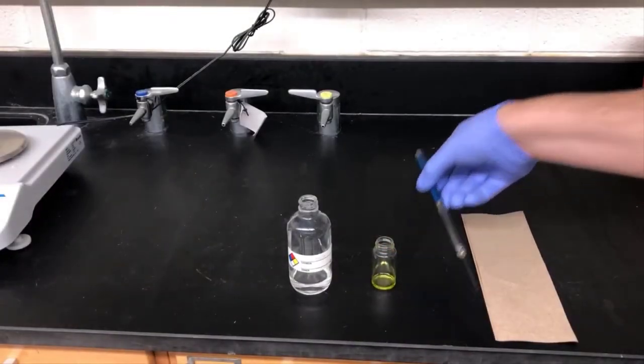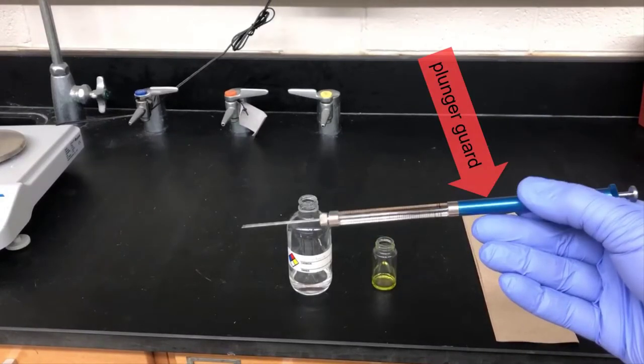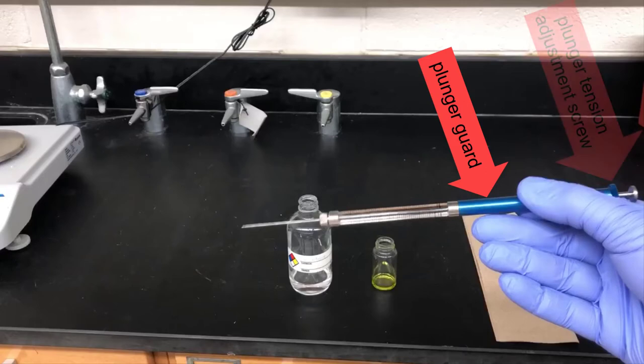Now it's time to work with the GC syringe. This is a 25 microliter syringe that has a blue plunger guard on it. It also has a screw top here that you can loosen or tighten to adjust the tension on the plunger.